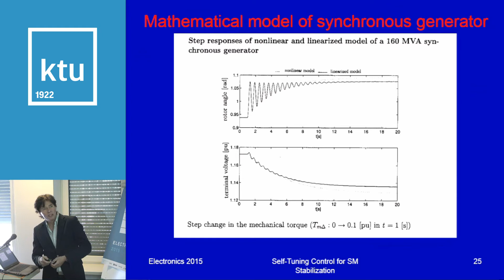Here are results showing the influence of different inputs on the outputs. First we change the mechanical torque of the synchronous generator by 5% for 10 seconds, then we change the second input, the rotor voltage, by 10% for 10 seconds. The change in mechanical torque produces large oscillations in electrical power, rotor angle, and rotor speed, but has small influence on stator voltage.